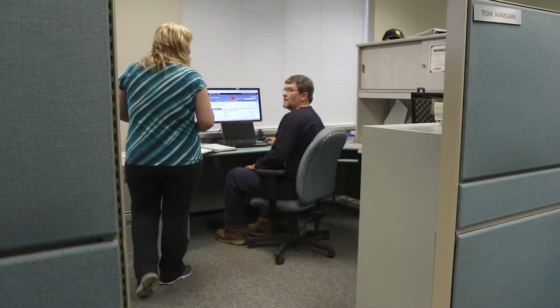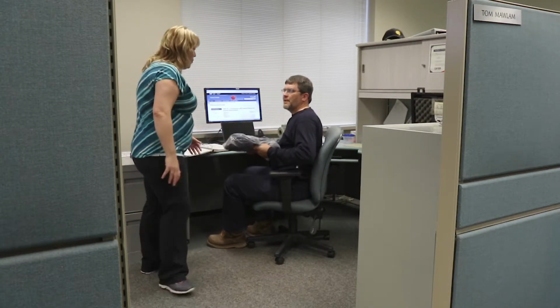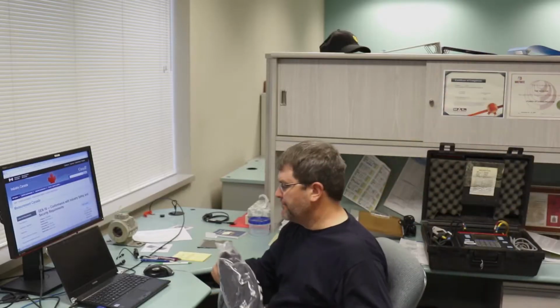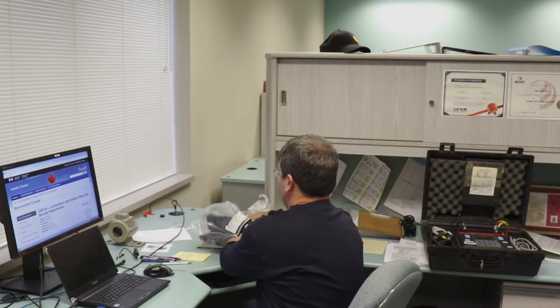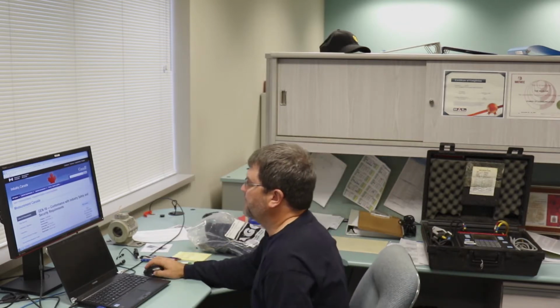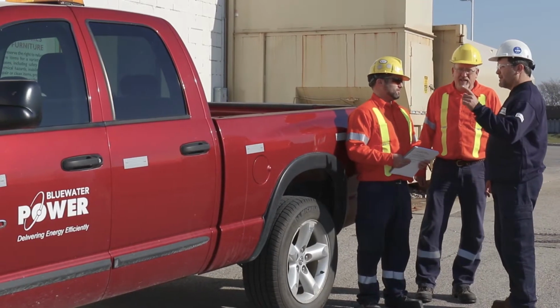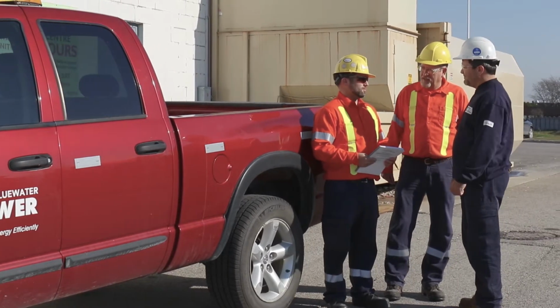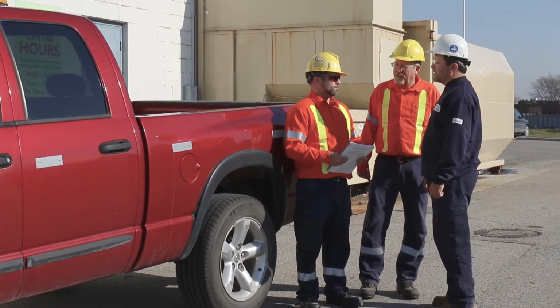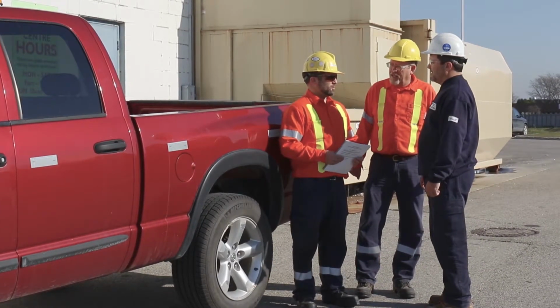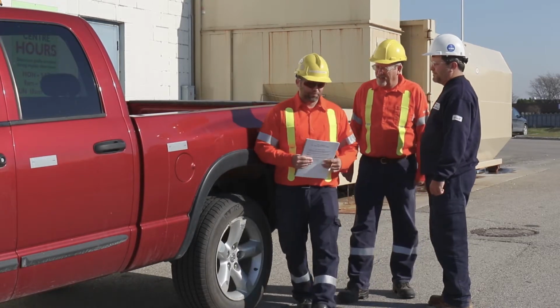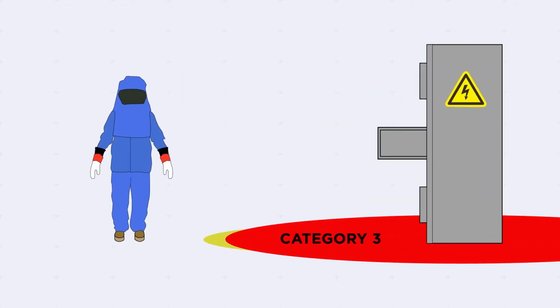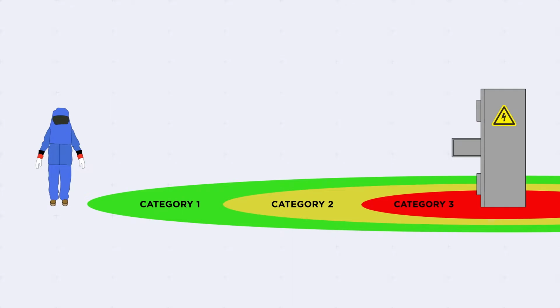Measurement Canada inspectors are provided with HRC-3 PPE for situations where the arc flash levels do not exceed 25 calories per squared centimeter. Follow all posted incident energy labels and consult with on-site personnel to determine the category of arc flash clothing required for the specific site. If it exceeds Category 3, remain well clear of the outer AF protection zone.